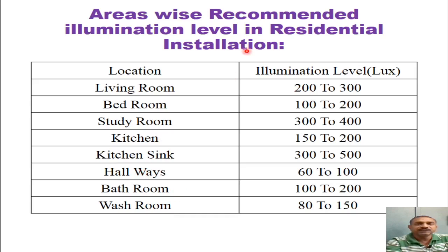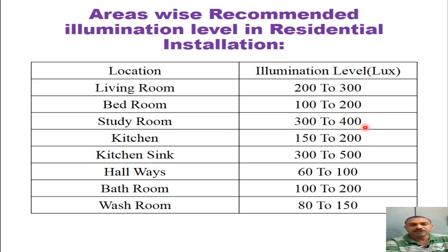Now let us see the area-wise recommended illumination levels in residential installations. The living room, or what we call the hall, should have an illumination level of 200 to 300 lux. The bedroom should have an illumination level of 100 to 200 lux. The study room, where a student or person is going to do reading, writing, or minute work, should have an illumination level of 300 to 400 lux.